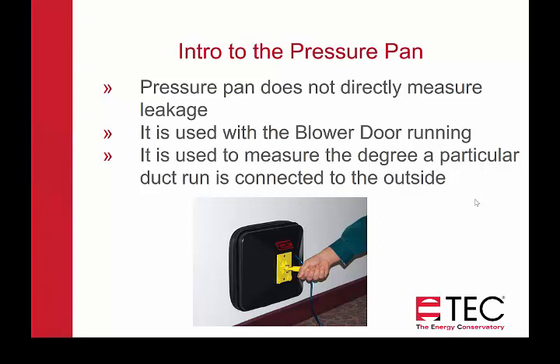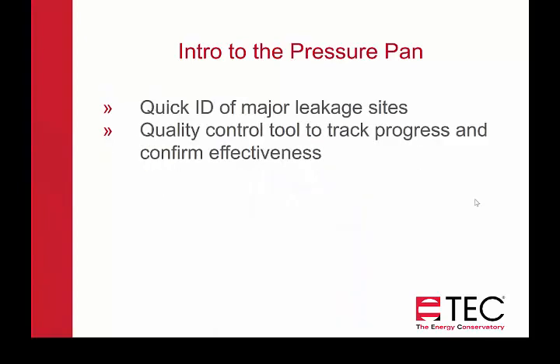When we're using the pressure pan to diagnose duct leakage, it's used with the blower door running. It's used to measure the degree a particular duct run is connected to the outside. With the house at 50 pascals, you're going around from register to register measuring the degree to which that particular duct run is connected to the outside when you're taking that test. It gives you a quick identification of where the major leakage sites are — the higher the number, the more leaky it is to the outside.